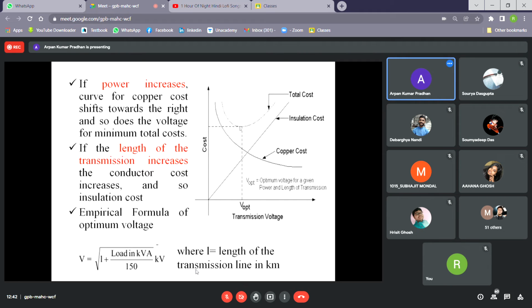Based on these observations, we have derived an empirical relationship between the voltage level and the point at which the cost is minimum. That relationship is V equals root under 1 plus load in kVA, divided by 150 kV. So based on how much your load is in kVA, you can decide what your transmission line voltage should be. That is the expression for voltage. Is that clear?